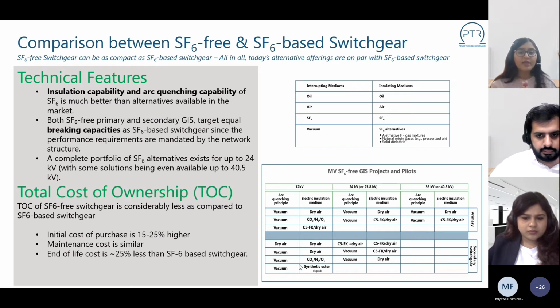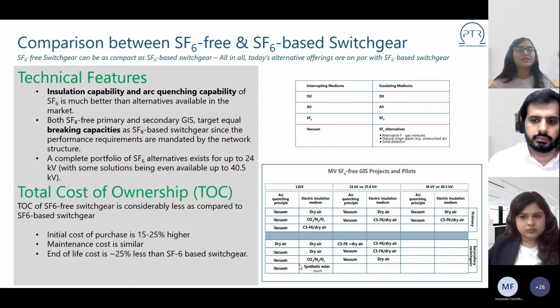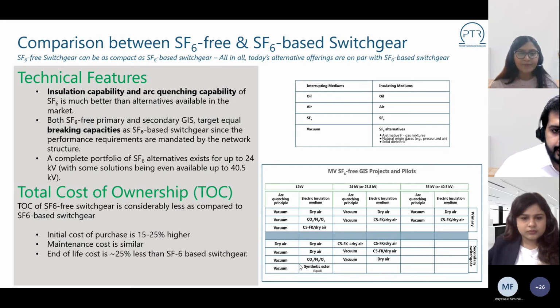Moving on, if we discuss the breaking capacities, SF6-free primary and secondary GIS target equal breaking capacities as SF6-based switchgear, since performance requirements are mandated by the network structure. However, if we look at the voltage and current ratings of the products offered as SF6 alternatives, they are currently available in the market up to 24 kV, and some solutions are available up to 40.5 kV as well. OEMs are continuously making efforts to make them more reliable and equivalent for the applications, and they are increasing the voltage and current ratings to be in line with application requirements.